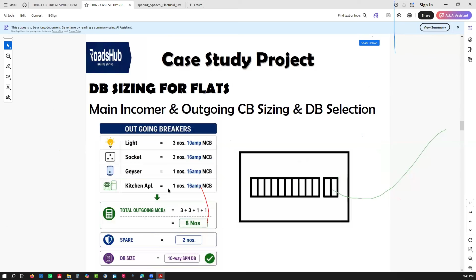So how do I go about the design? You calculate your current. So the same formula I've talked about. If it's a 3-phase system, automatically it needs to be a 3-phase system because you're supplying the entire floor. So you have your current, but you're using 46.2. Just remember, it is per floor. So to get the main incomer, you do the current value, that's 80.4. Do a safety margin, that's 100.5. The nearest you'll go for is a 125. You see now, that design, people can do without mathematics. As long as you know how much current you need, you can actually just say, I need a 125.